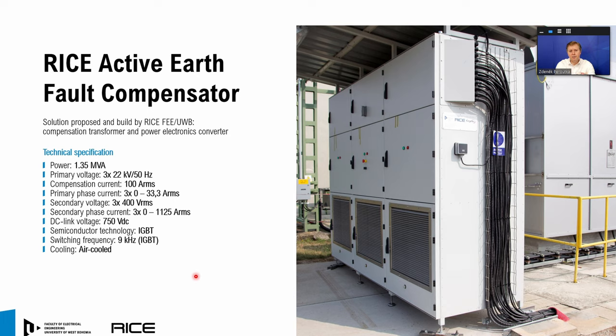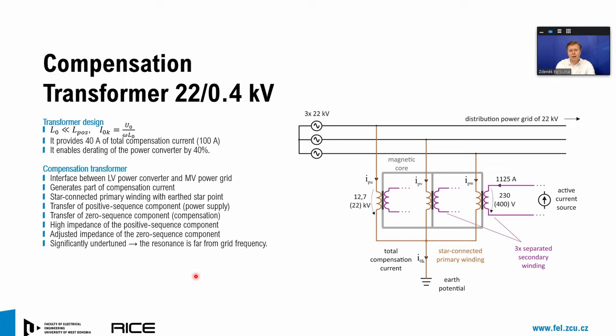Based on this idea, we developed in RICE a first prototype of this device having a rated power of 1.35 megavolt amps, and this prototype is dedicated to installation in a power grid with a rated voltage of 22 kV and offers a compensation current of 100 amps RMS. The device has two main components. It is a compensation transformer, and in the first generation we developed a low voltage converter which is connected to the secondary winding of this transformer.